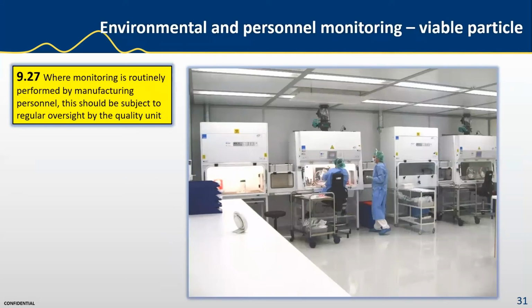Section 9.27, where monitoring is routinely performed by manufacturing personnel, this should be subject to regular oversight by the quality unit. Aseptic operations, including, let's say, APS, for example, should be observed on a regular basis by personnel with specific expertise in aseptic processing to verify the correct performance of operations, including operator behaviors in the clean room, and address inappropriate practices if detected.